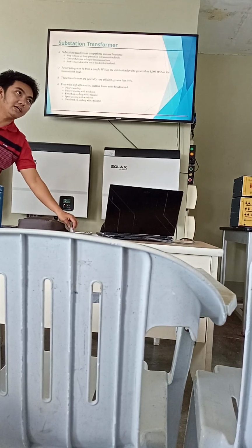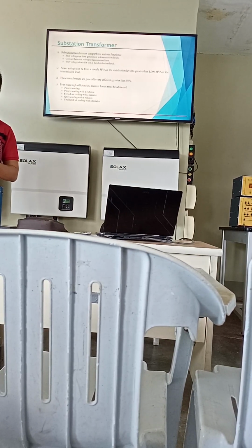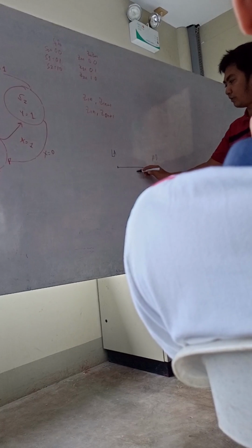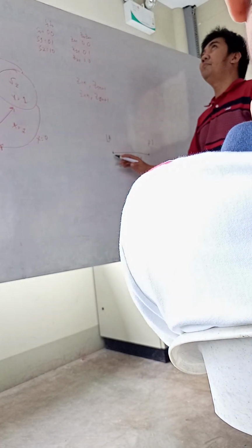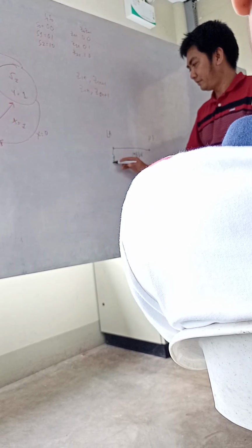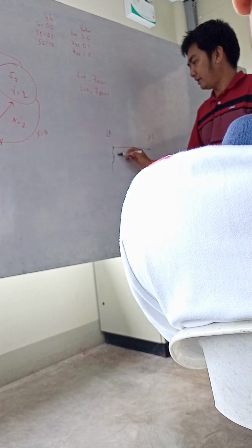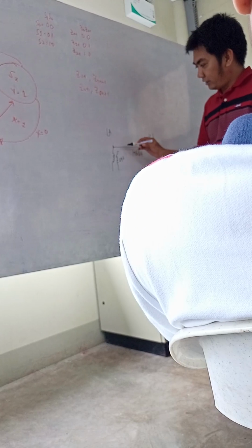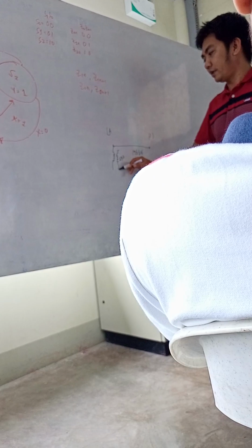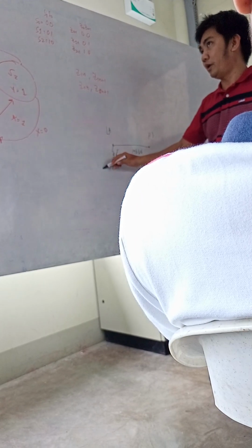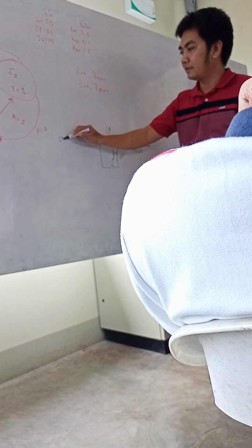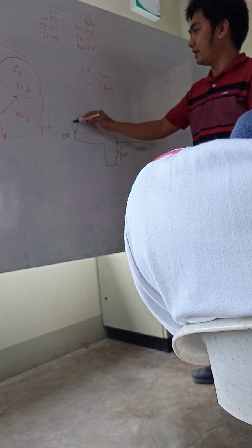What is interesting at the NGCP substation is that it has 138 kV or 69 kV. For a long time, we have had 138 kV from, let's say, the Lanao area to Misamis Oriental. What they do at Abaga substation is a transformer that transforms from 138 to 230. This 230 kV line was constructed due to the MVIP, the Mindanao-Visayas Interconnection. That is the voltage requirement for the interconnection, heading to Lala substation, and then in Lala there is also the converter station.